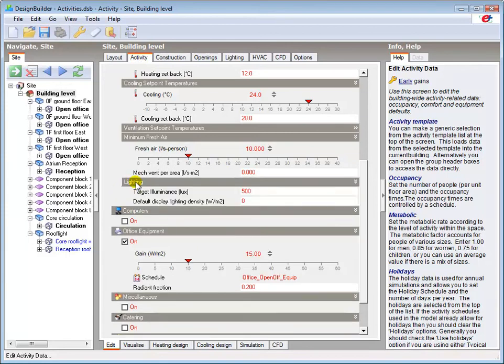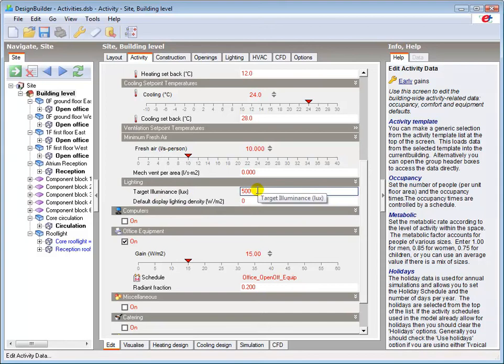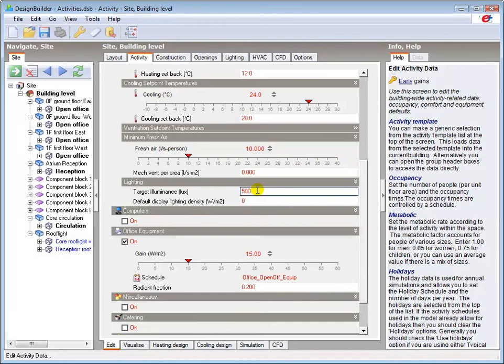The default target illuminance again relates to the activity type, whereby an office will require a higher lux level than, say, a storeroom. An increased target illuminance level will increase the energy consumed by the lighting systems and the related internal heat gains.